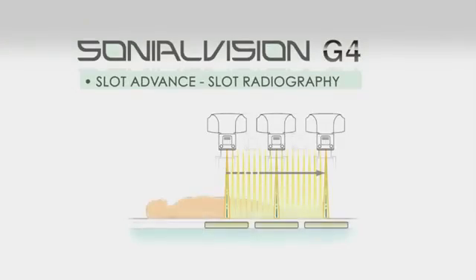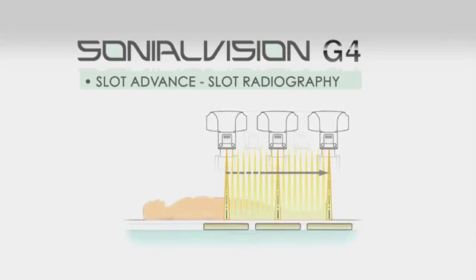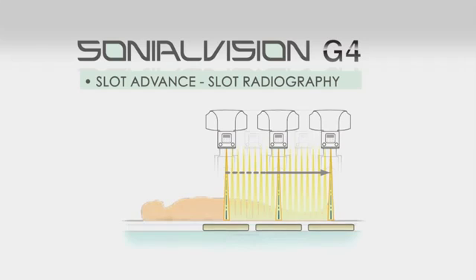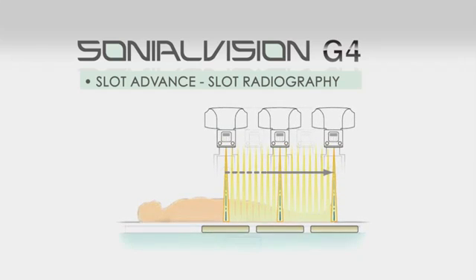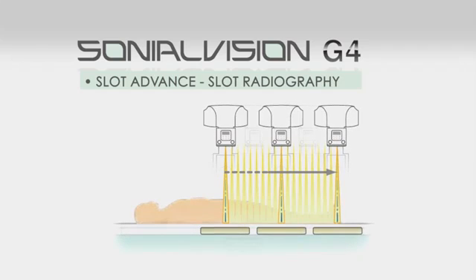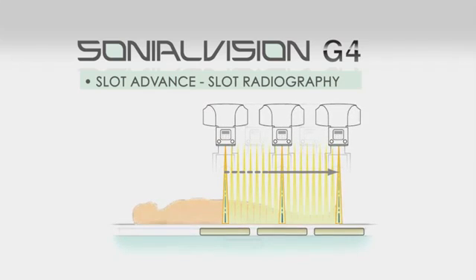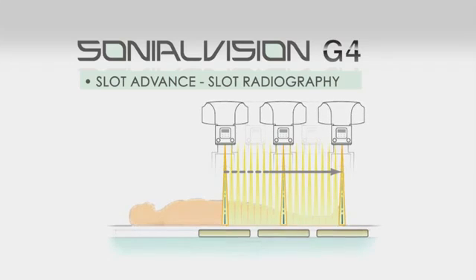Slot Advance, Shimadzu's slot radiography application, collimates the X-ray beam so that it only exposes a narrow central slit field without distortion caused by oblique rays. These central slit images are captured using the SonialVision's super high-resolution flat panel detector by moving it in parallel with the X-ray tube.